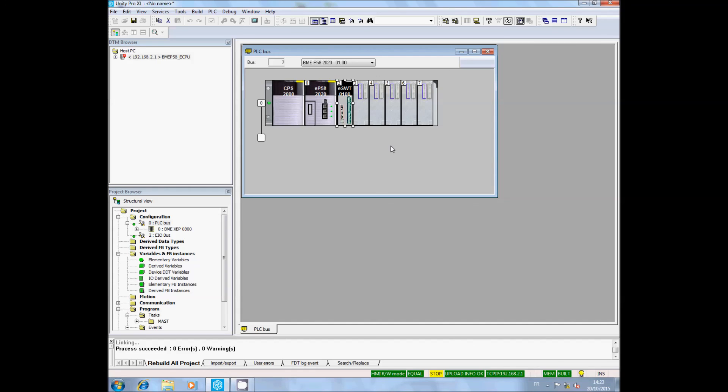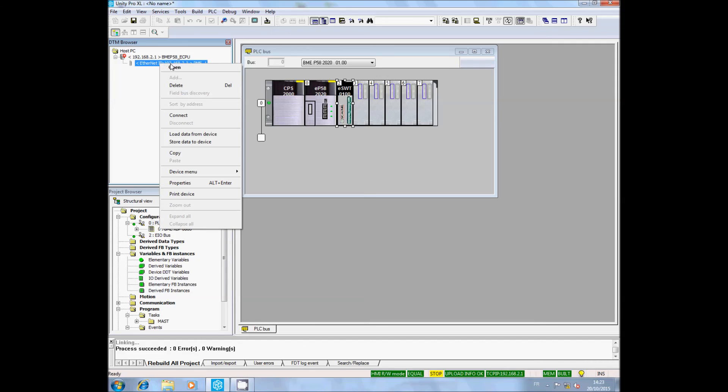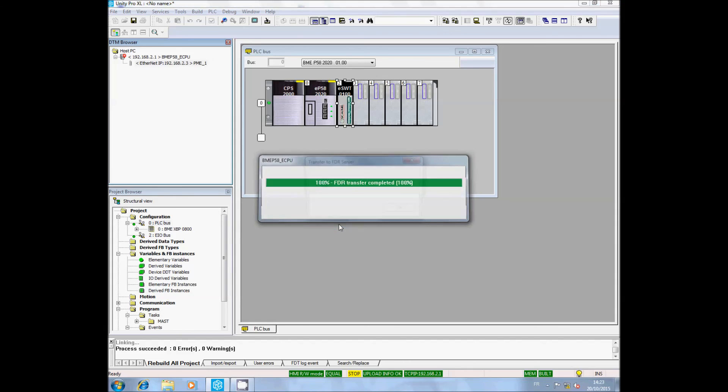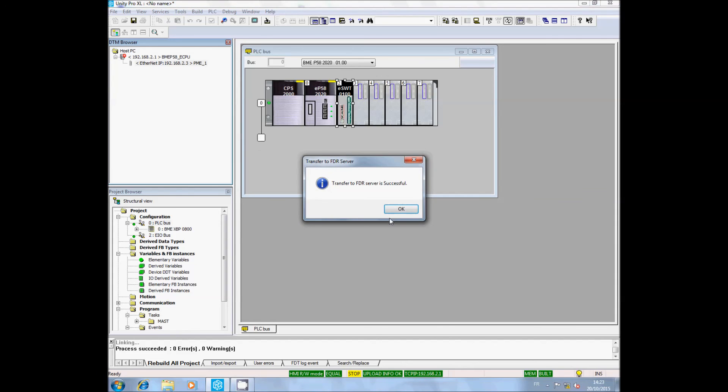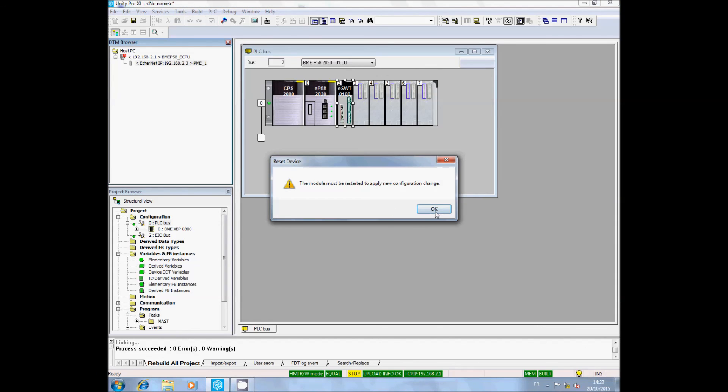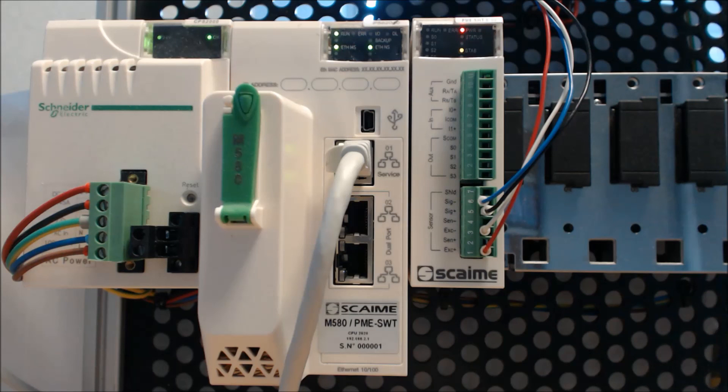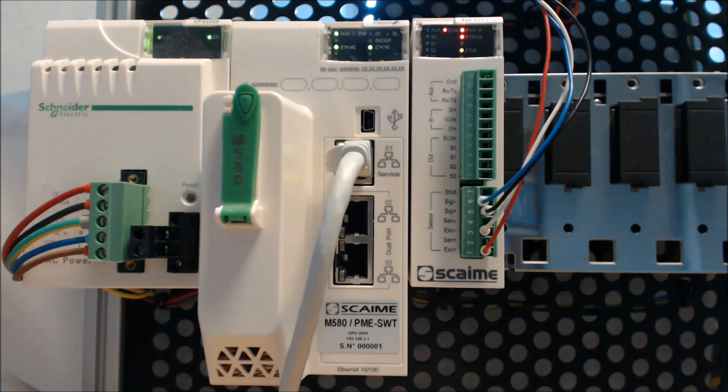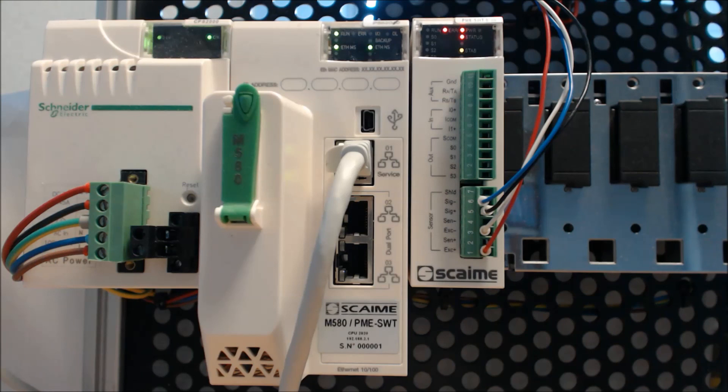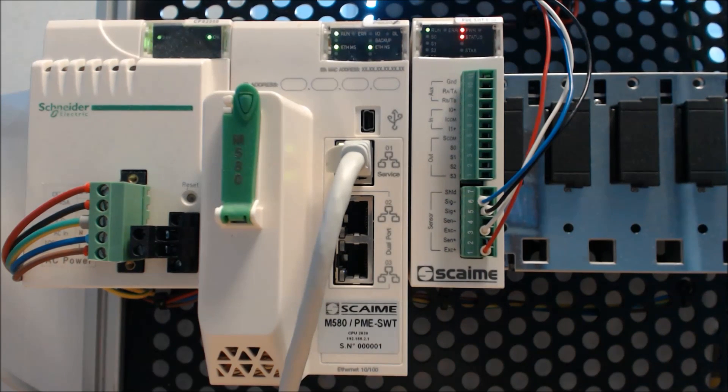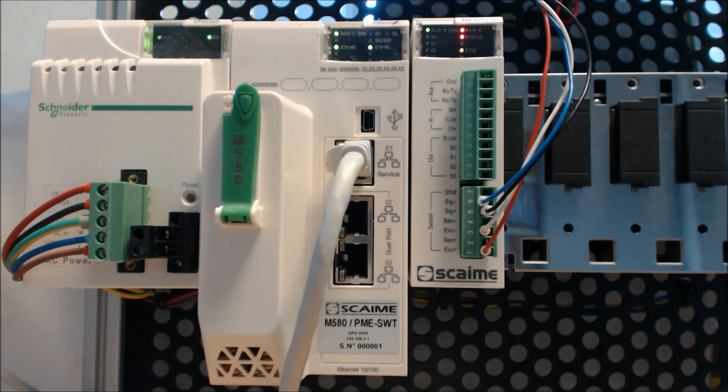To do that, right-click on the PME DTM, select your device menu, then select Additional Functions and click on Transfer to FDR. The system will confirm OK, then inform you that the PME SWT needs to be reset. Validate it. After a few seconds, you will see the PME SWT reset and the RUN LED will light up in green.